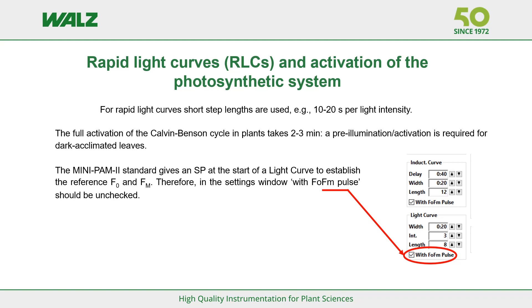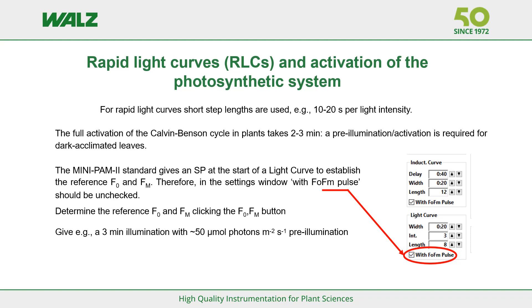Rapid light curves represent a somewhat different challenge. Light steps of maybe 10 or 20 seconds are used, but activation of the Calvin-Benson cycle takes 2–3 minutes. If a rapid light curve experiment is carried out with a dark-acclimated leaf, experimental artifacts are almost unavoidable. For the Minipam 2, the following protocol is suggested when dark-acclimated leaves are used: turn off the initial saturation pulse by unchecking 'initial pulse'; determine the reference F0 and Fm by clicking the F0Fm button; give a manual 2–3 minute pre-illumination of, for example, 50 µmol photons m⁻² s⁻¹; and finally start the light curve. Thank you for your attention.